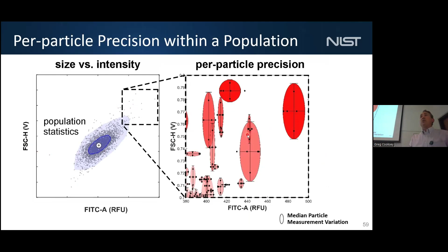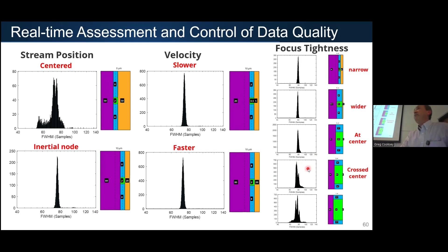So if we are center focused, the distribution of fluorescence intensities is a mess. If we put them on the inertial node, we very carefully reconstruct the distribution of the population. We can actually speed up the flow and maintain the distribution of the population. So this is also the only cytometer in the world that gets better at faster flows. That's pretty cool. And then we can control the ratio of the sheath to core, the size of the sample, the amount of sample going through volumetrically through the system. We can increase the volume of the core up until the point that the core crosses the center line, and then you see the measurement variations start to increase.